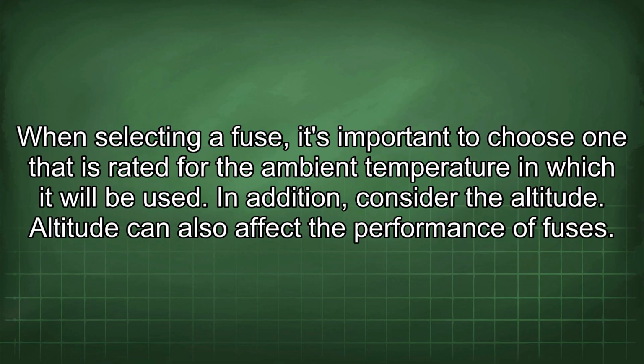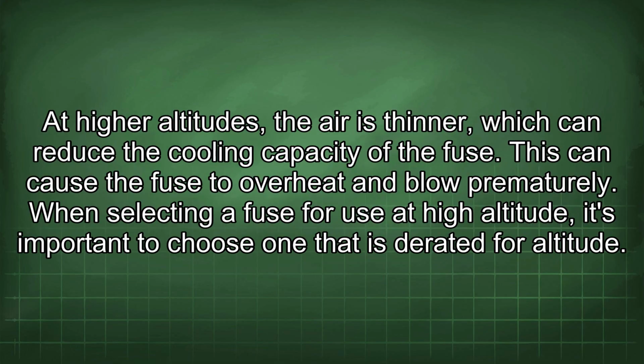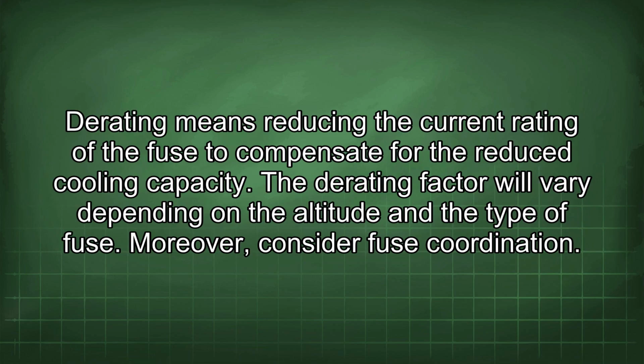When selecting a fuse, it's important to choose one that is rated for the ambient temperature in which it will be used. In addition, consider the altitude. Altitude can also affect the performance of fuses. At higher altitudes, the air is thinner, which can reduce the cooling capacity of the fuse. This can cause the fuse to overheat and blow prematurely. When selecting a fuse for use at high altitude, it's important to choose one that is derated for altitude. Derating means reducing the current rating of the fuse to compensate for the reduced cooling capacity. The derating factor will vary depending on the altitude and the type of fuse.